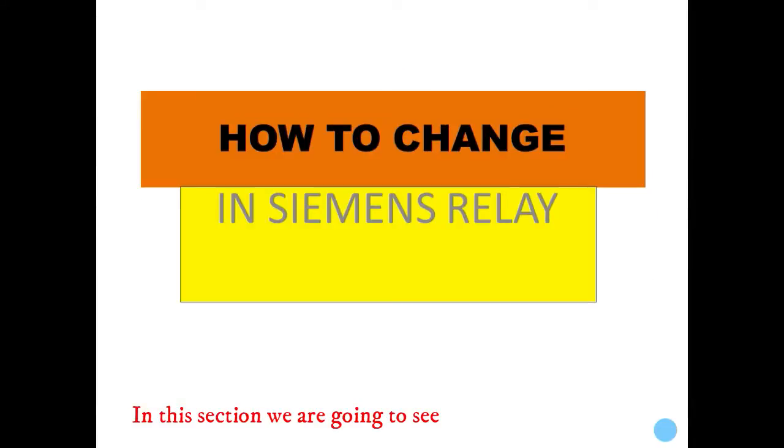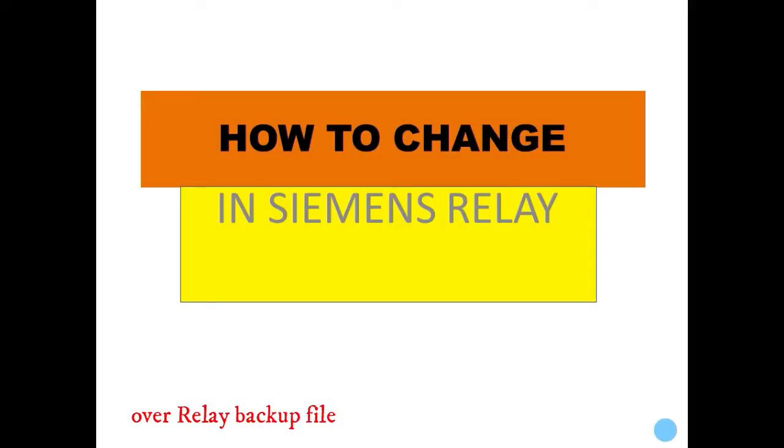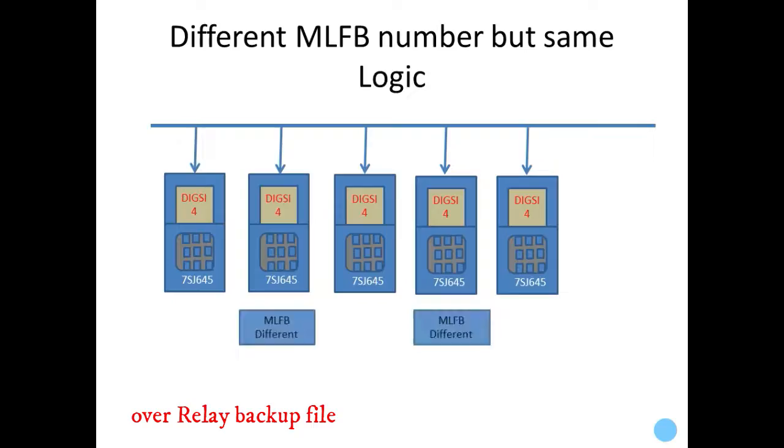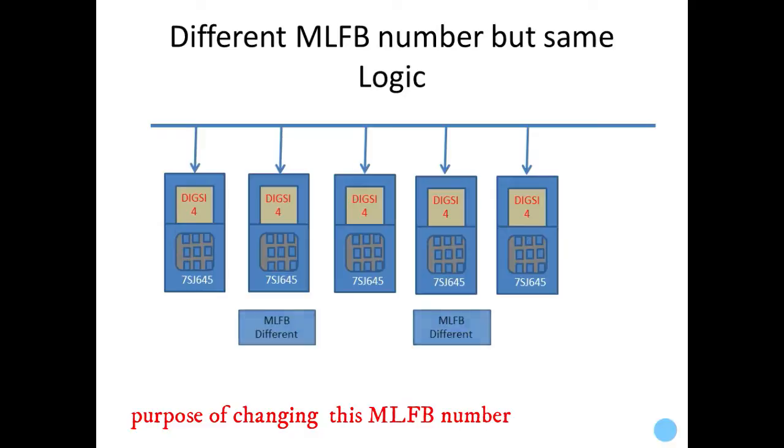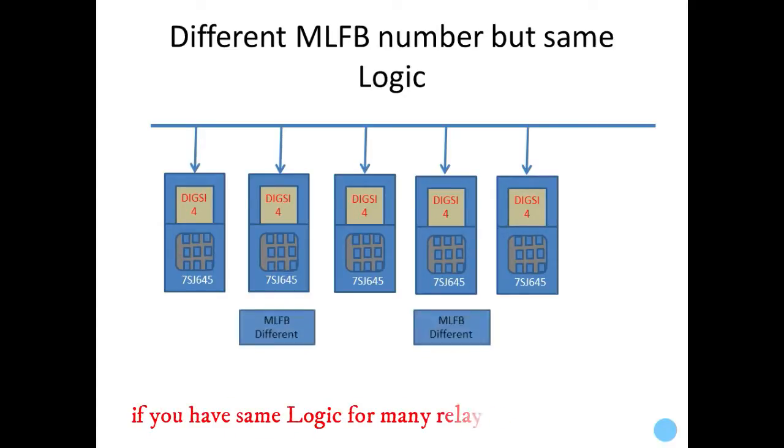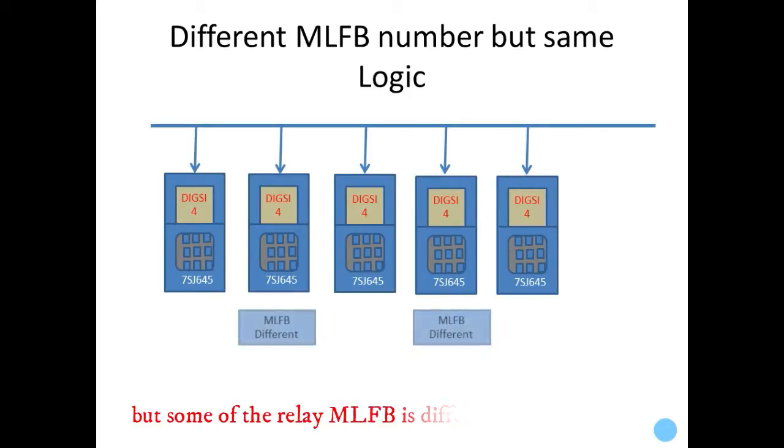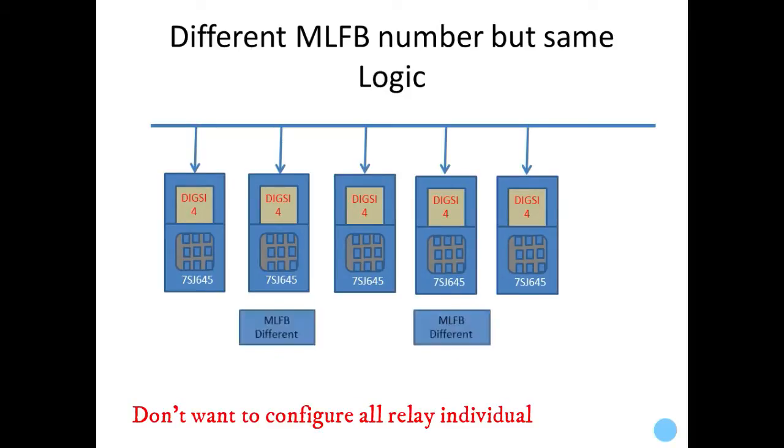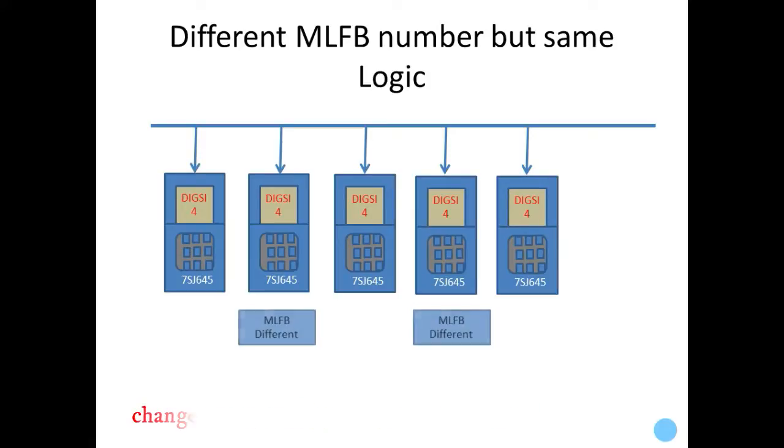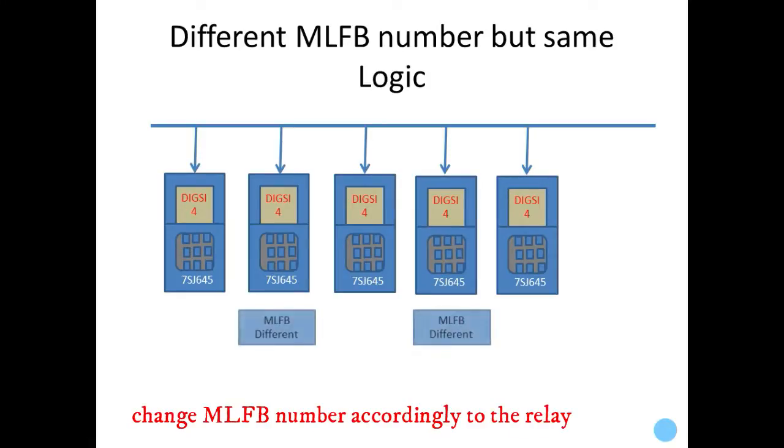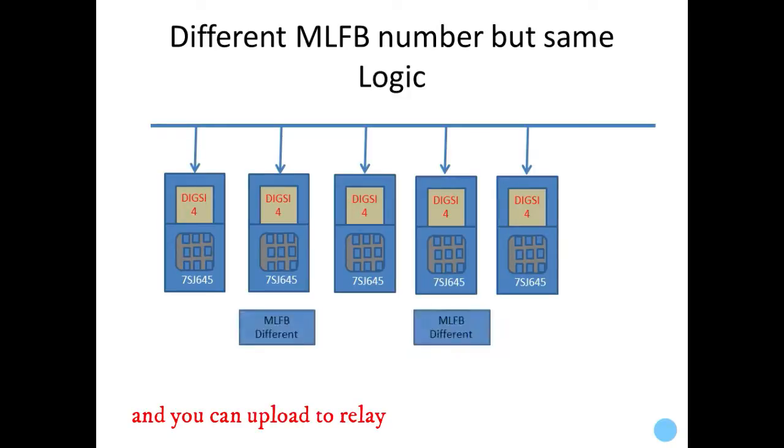In this section, we are going to see how to change the MLFB number in a relay backup file. The purpose of changing this MLFB number is if we have the same relay logic for many relays but their MLFB is different. If you don't want to configure all relays, you can change the MLFB number according to that relay and upload the settings file.